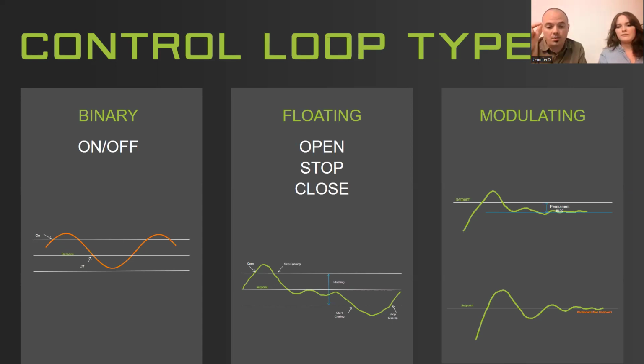So for our program to make a floating loop work properly, we're going to take that into account. Say we want to achieve a 50% open valve; well, we're going to send an open command for 45 seconds. Using that similar idea, we're going to be sending the commands to open or close to achieve a relative position, in this case a valve position, as it is needed to satisfy the temperatures. So the problem with the floating, there are some advantages to a floating strategy, and it usually involves costs.